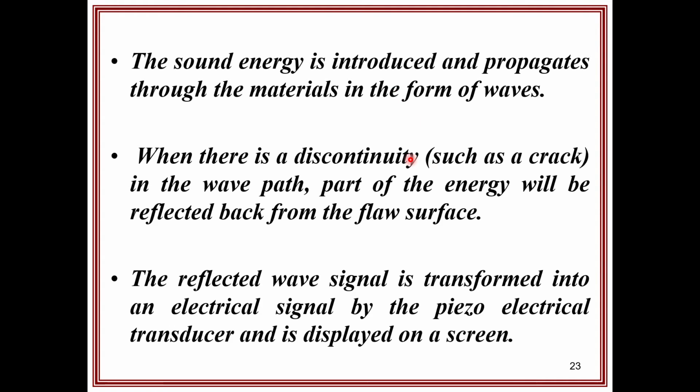When there is a discontinuity in the wave path, part of the energy will be reflected back from the flaw surface. So what will happen if there is any obstacle in the path of the sound energy, or if there is any hole or crack present? If the sound waves are traveling through that portion where the crack is, then some of the sound waves will reflect back. The remaining sound waves will travel inside the material to the end of the material.